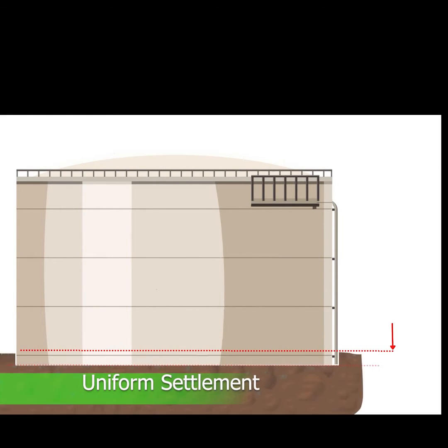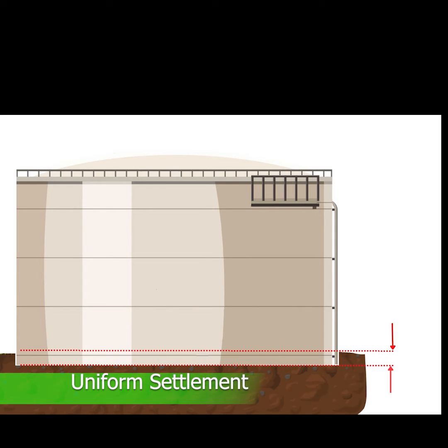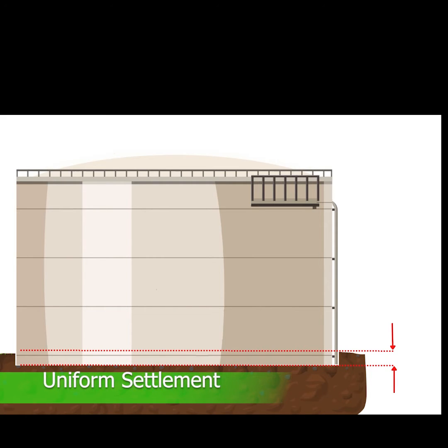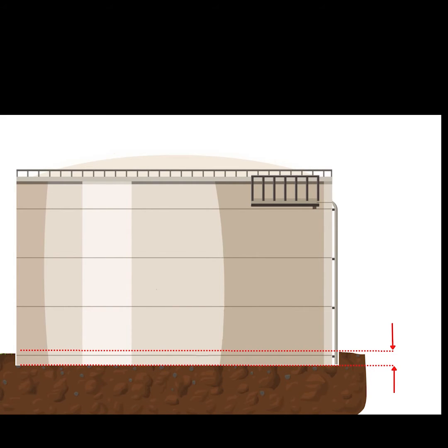Uniform settlement of a tank does not induce stresses in the tank structure. However, piping, tank nozzles and attachments must be given adequate consideration to prevent problems caused by such settlement.